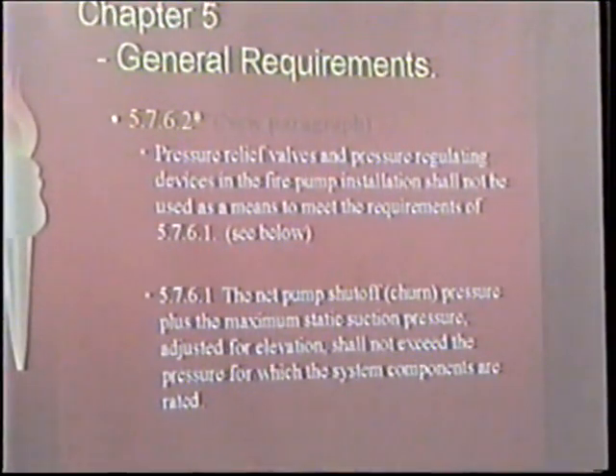Well, I think that paragraph there specifically is aimed at those that use the variable speed pressure regulating controls, because there the system has to be designed to withstand whatever the discharge is going to be with the pump locked and bypass, which means it's running rated speed, maximum output, and you get what you get. So if you're over the 175 at that point, you're going to be 300 pound all the way to where that pressure drops off on the elevation of the building. That's just the way it's going to be.